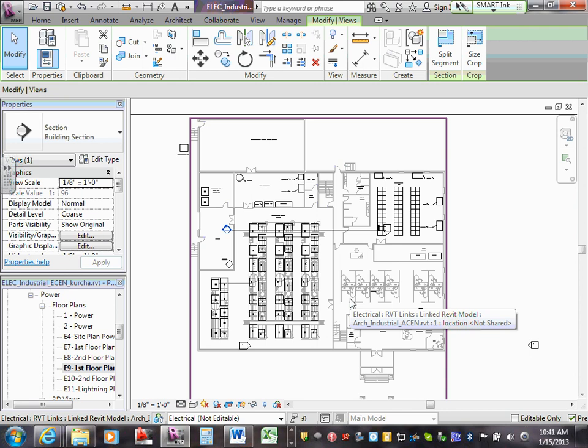There's all calculations that you gotta do when you're submitting to the authorities, the fire marshals, for your permits. You have to do calculations on your amperage, your power draw, your battery life, your battery draw on the devices. And then when you go to do your test, all these devices have to take the power off for 24 hours, and then they have to run for 5 minutes straight. If they're asking for more codes, you have to size your batteries properly, because some of them will say go 24 hours without power and then run for 15 minutes straight. And the fire marshal will make you do that on one of them.